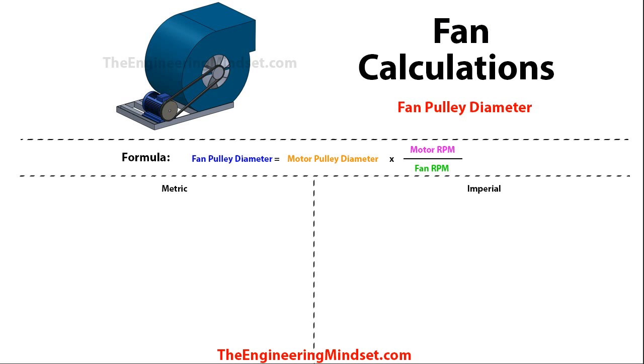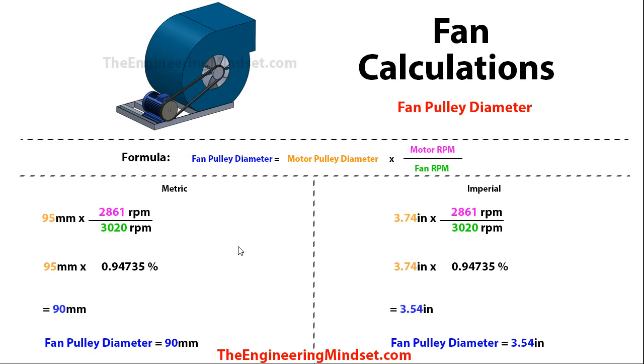So the first one we're going to look at is calculating the fan pulley diameter. You can see I've split the screen into two here, so we're going to have the metric and imperial calculations. I've tried to colour code everything throughout the video — I find it just makes it a lot easier to follow the numbers. The formula we need is: the fan pulley diameter is equal to the motor pulley diameter multiplied by the motor RPM divided by the fan RPM. We can get these figures from the manufacturer, or if you haven't already purchased the equipment, you can look it up online. For the fan, that's going to be the RPM you need to provide a certain ventilation or airflow rate. And for the motor, this is the RPM that it's going to rotate at.